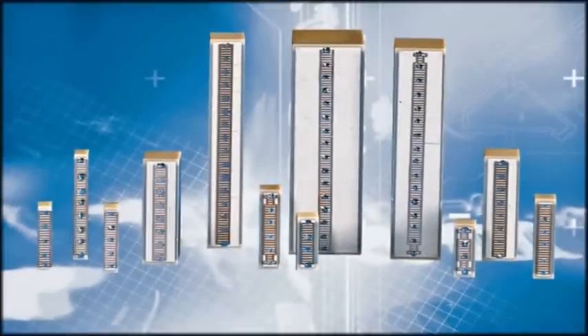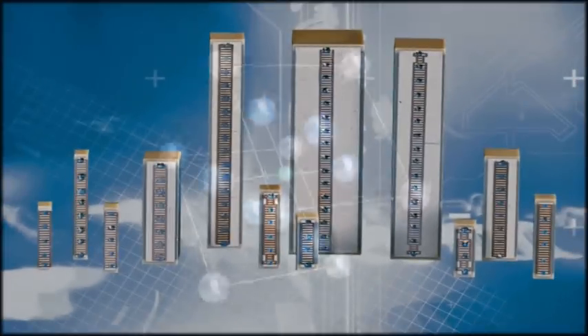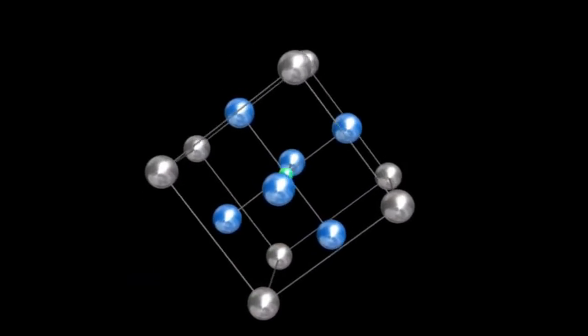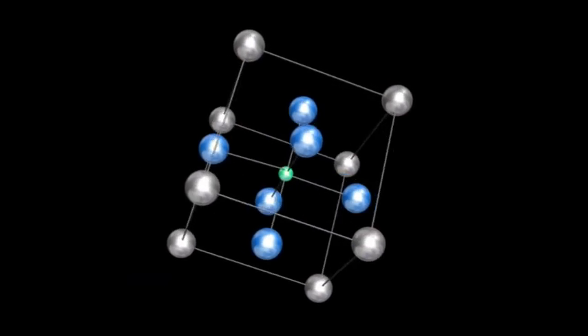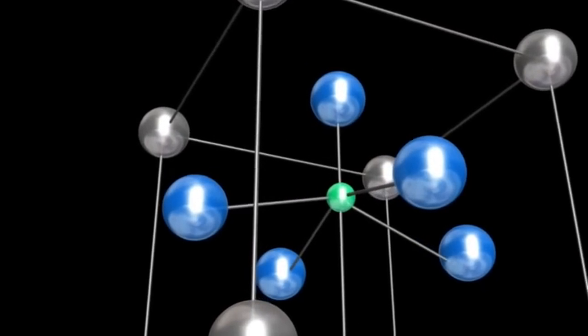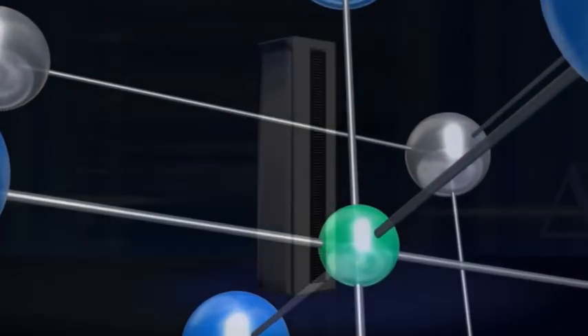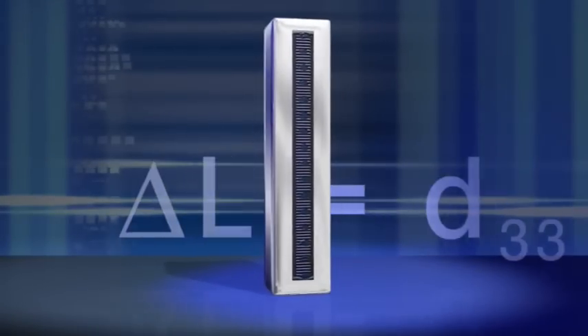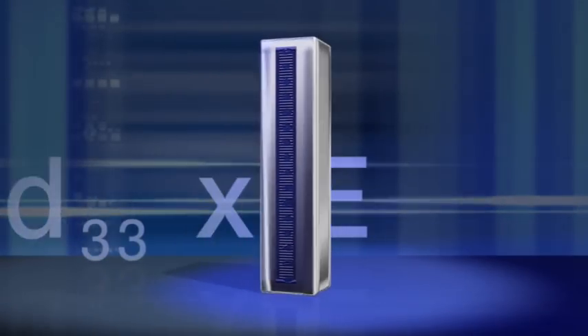At the heart of piezoelectric positioning technology is the piezoceramic actuator. It has a crystalline structure which expands slightly when an electric potential is applied. Known as the inverse piezoelectric effect, this property is exploited by nanopositioning technology. By changing the voltage applied, very precisely controlled motion can be performed.